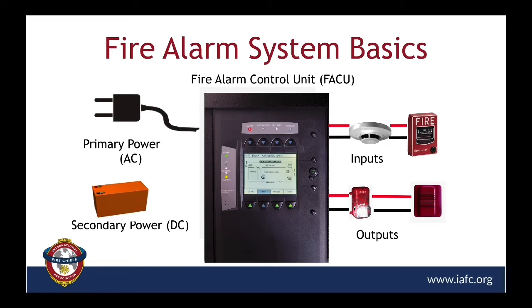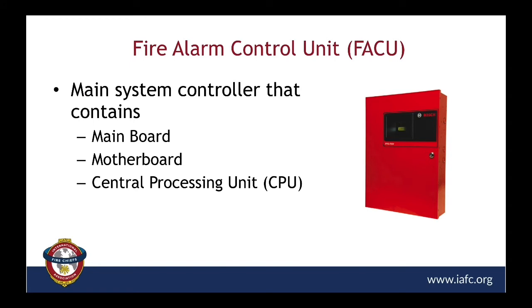So now we're going to do a little deeper dive into these various components. So, Richard, one of the things that a lot of company officers see is they'll get a building fire alarm when the area loses power. With this slide, you're kind of saying that's not normal, right? You should get a trouble condition if there's loss of primary power, but you would not get an alarm condition. So typically, I know in our jurisdiction, when our companies do get to this, there are times that for some reason the alarm system's maybe doing something it shouldn't be, but the secondary power should cover it. And if it doesn't, or activates the building alarm, that's a good time for that company officer to flag it to their fire marshal or something along those lines as well. Absolutely. And I'll get into a little bit more about secondary power supplies, which I think is very important.